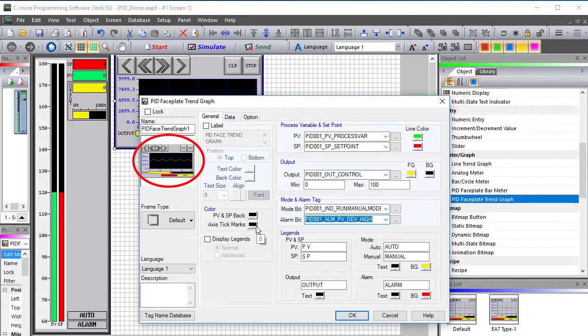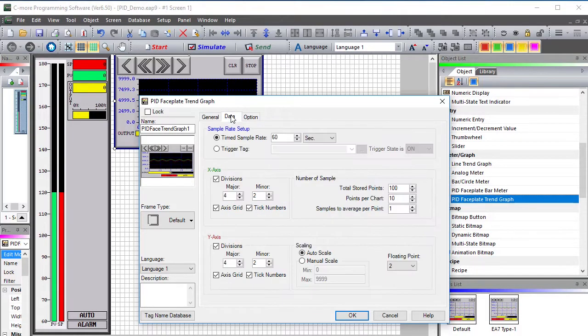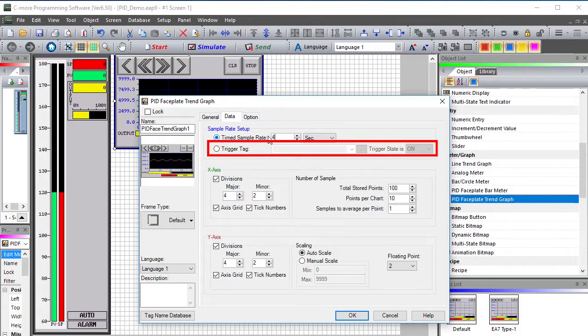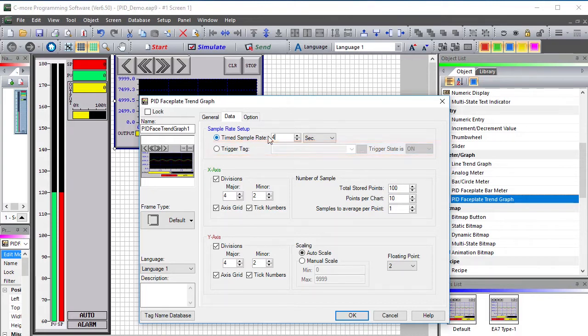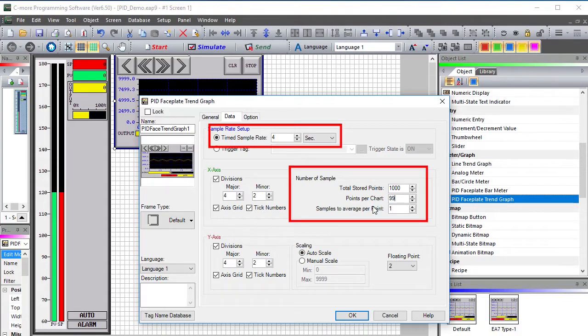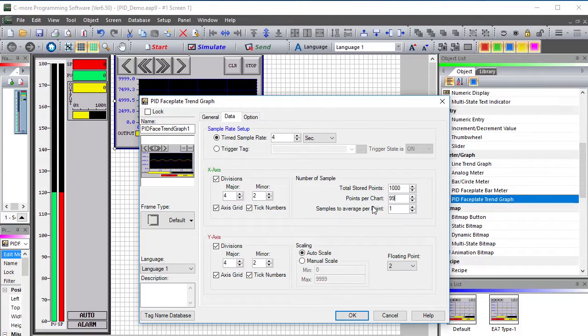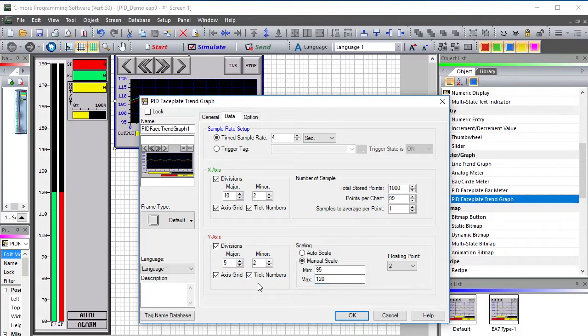I love that I can see a preview of what I'm about to get. Moving over to the data tab — this is key. You need to choose a sample rate that is appropriate for your process. I'll put 4 seconds in, or better yet, you could have the sample rate controlled by the PLC. Let's store 1000 points and max out the number of samples shown on the display. The key is to play with these settings until you get the display you want. Let's make the X axis 10 divisions to make it look more like the PID monitor, and force the Y axis to cover just the range we'll be operating in with an appropriate number of tick marks.